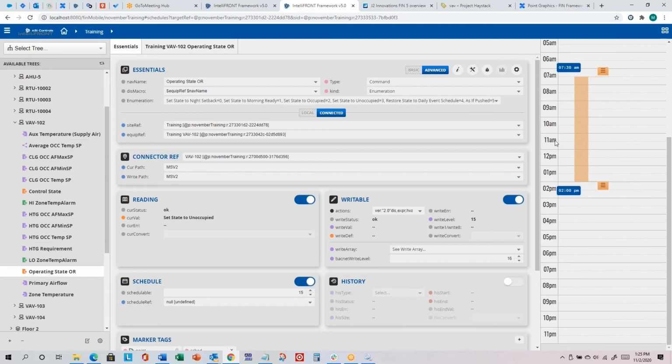But we potentially could get into a little bit of a vicious circle here because we're going to have all 3 of our front ends writing to all of our VAVs, and sort of the last write wins. And that's unusual. Usually, almost always, there's 1 front end per system. So this is a bit unusual, but I think it's helpful that we all can see each other's controllers.